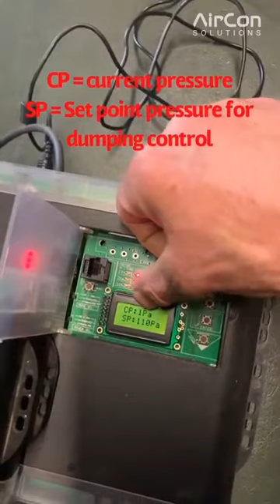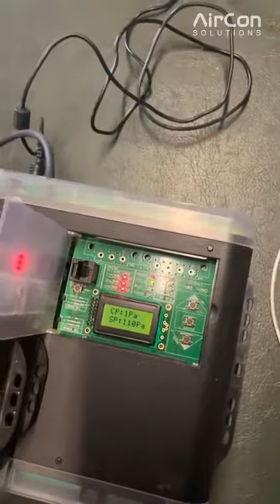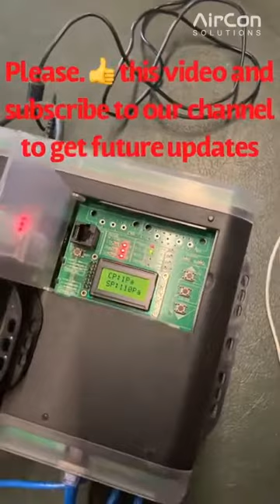So now the system, before it was reading 21 pascals, and now that we've recalibrated, it's reading at 1 pascal. So it's now recalibrated back to the current atmosphere pressure. That's how we go through and reset the pressure sensor module.